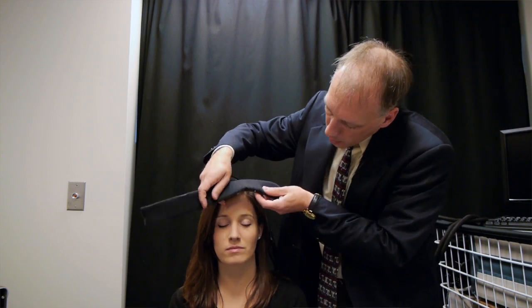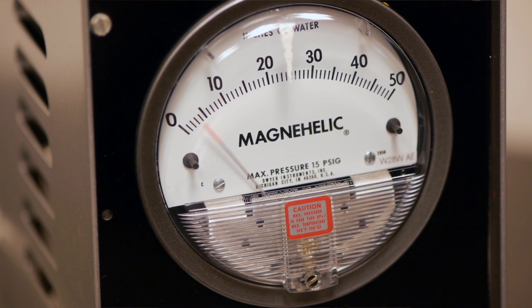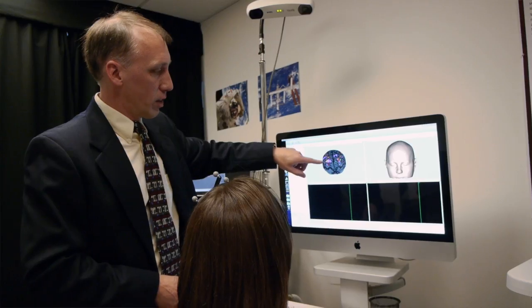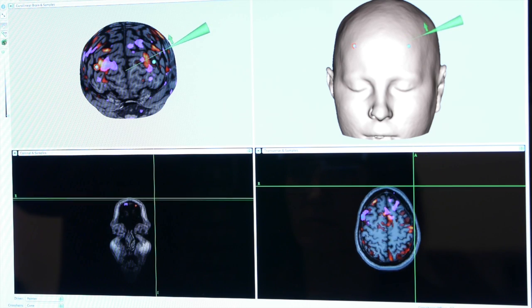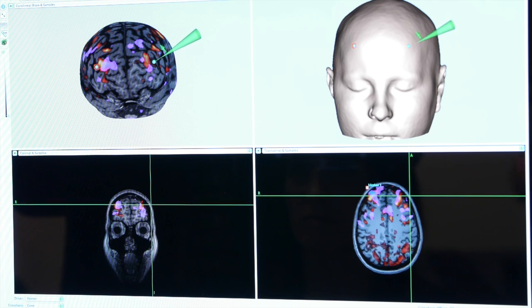Our device will allow us to monitor the blood oxygenation changes and the blood volume changes that might be related to elevated pressures. The idea is you shine near-infrared light into tissue, and then from a detector you measure the light that comes out. It's completely non-invasive — you just place it on the skin — but it allows us to measure the surface of the brain with a sensitivity pretty close to that of a functional MRI.